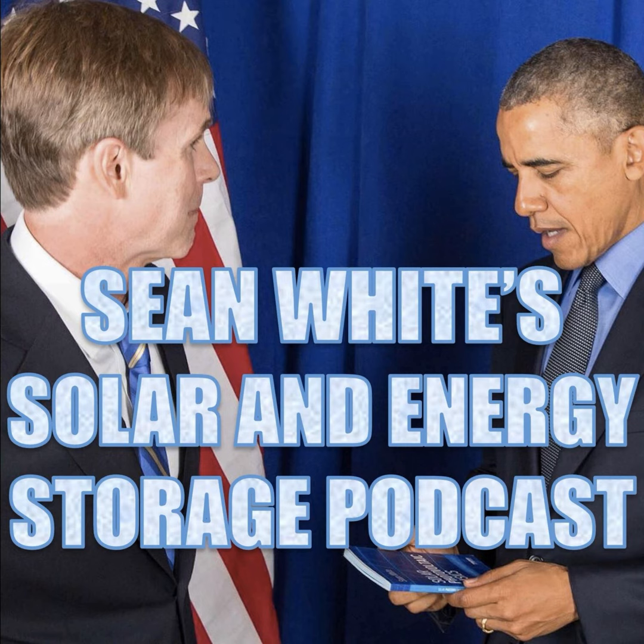Interactive inverters can come in all sizes. The popular small interactive inverter is called a microinverter. A particular brand is called Enphase, and they are the second biggest inverter company on the residential market in the United States. And these inverters do anti-islanding on a PV module basis. On the other hand, you can have huge interactive inverters that are multiple megawatts in size. All these inverters do UL 1741 anti-islanding. That means that when the grid goes down, they turn off. They can't send out power without a grid.